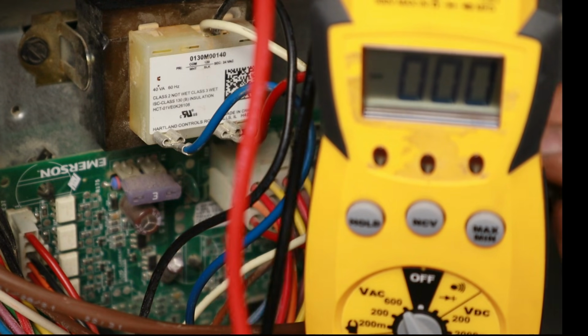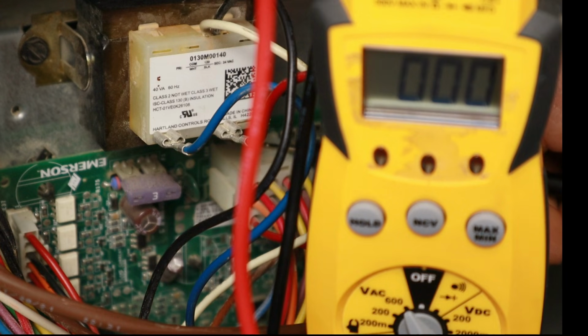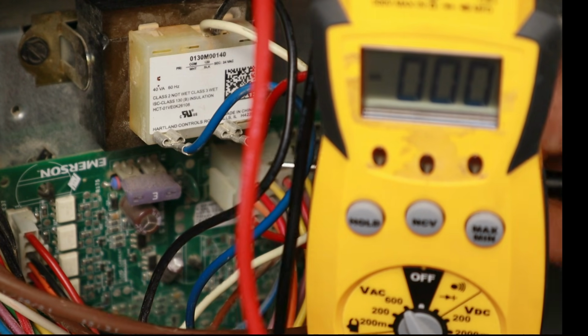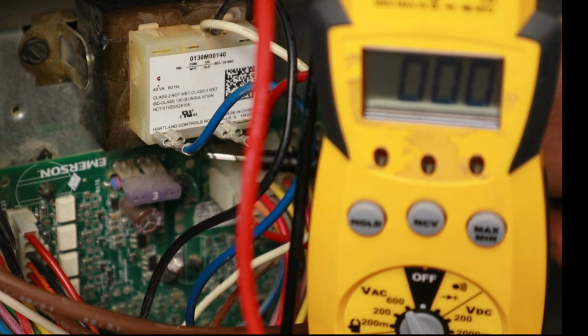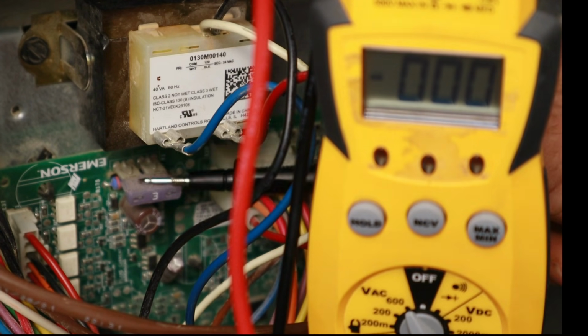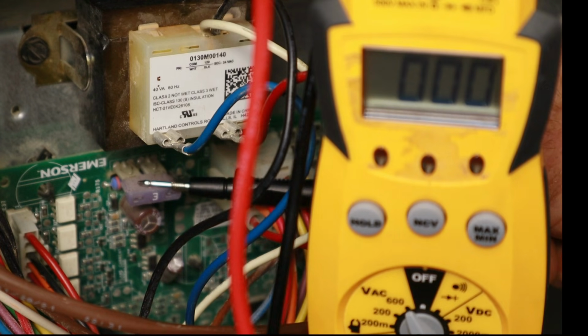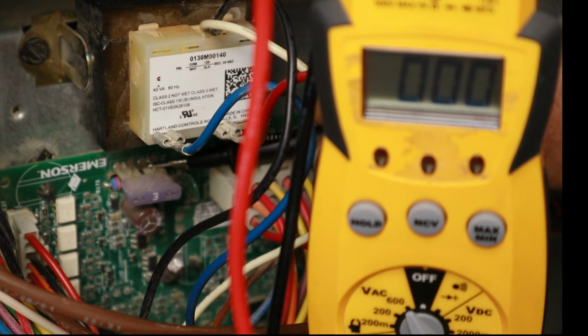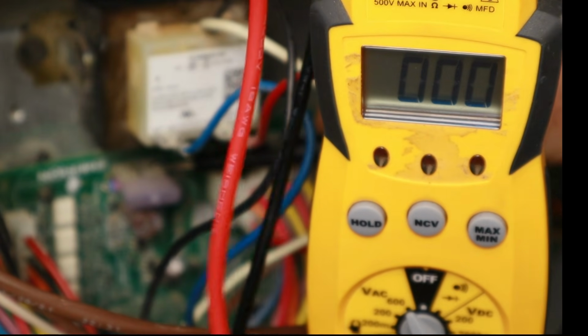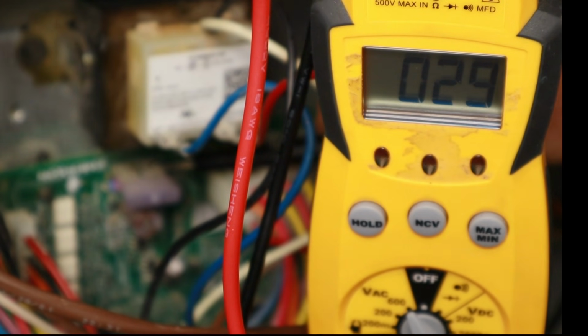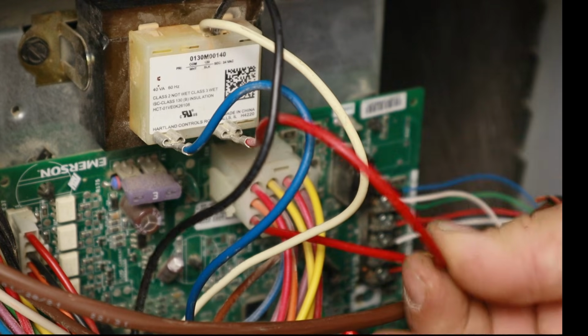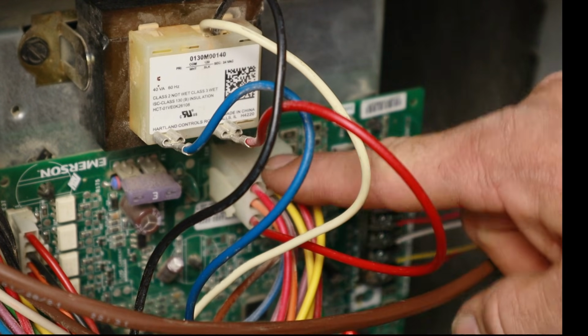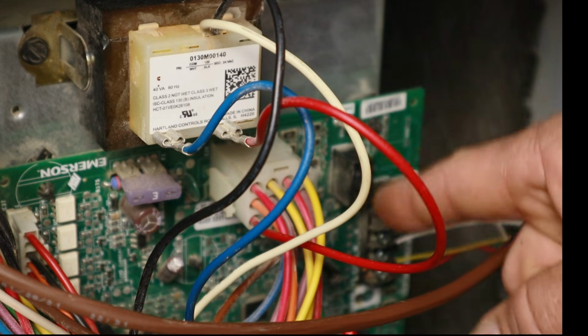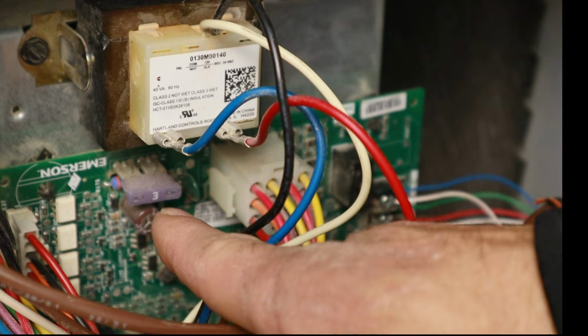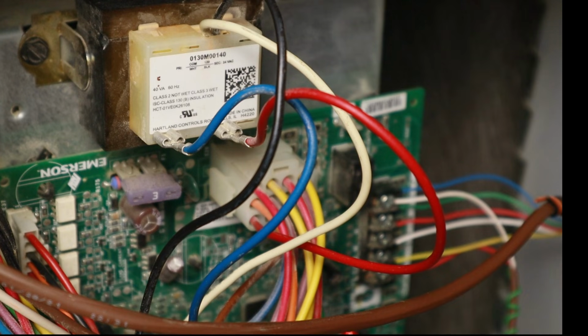So in order for me to test to make sure that red wire and the 24 volts is going into the control board just fine, instead of pulling that Molex plug off and sticking my probes in the Molex plug, what I can just do is go right to the fuse and test for power there, because that's the first place it's going to go anyway. So I will put one probe on the fuse there. I will go to ground, and you can see I'm reading 29 volts. So what that's telling me is my 24 volts coming off my transformer, it's going into the Molex plug, it's feeding back into the control board, and it's making it to the fuse. So I'm good up to that point.